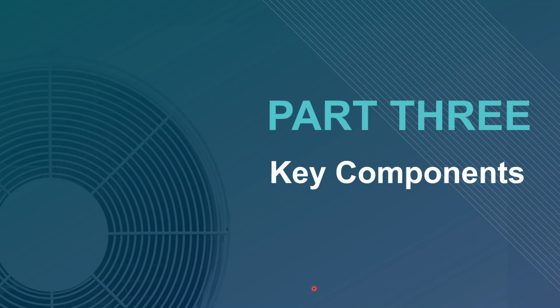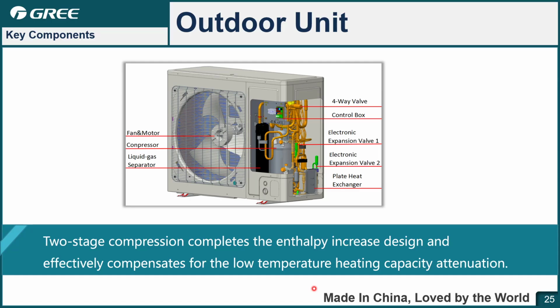Then the second part is about the components. First one is the split VERSATI 3 outdoor unit. When you get the unit, you remove the front casing, and you can see all of the major components, such as the fan motor, compressor, liquid gas separator, and a plate heat exchanger. This is the equalizer, and the electronic expansion valve to control the refrigerant throttling.